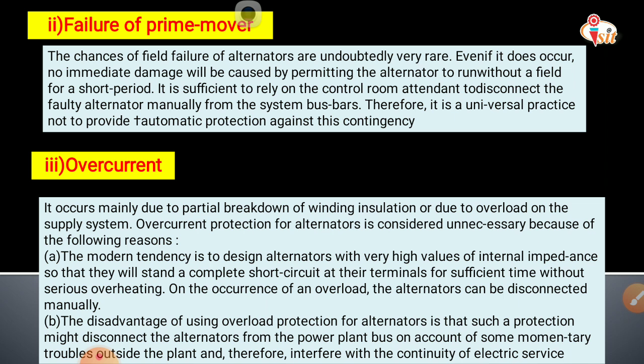The second fault is failure of field. Chances of field failure in alternators are very rare, and even if it does occur, no immediate damage will be caused by permitting the alternator to run without a field for a short period. It is sufficient to rely on the control room attendant to disconnect the faulty alternator manually from the system busbar. Therefore, it is universal practice not to provide automatic protection against this condition.